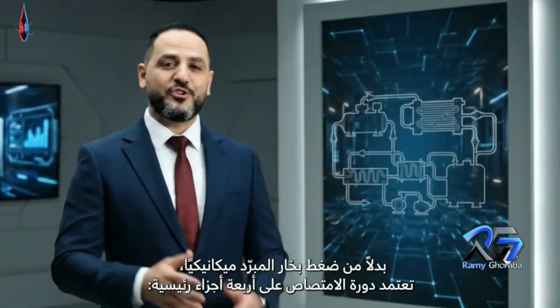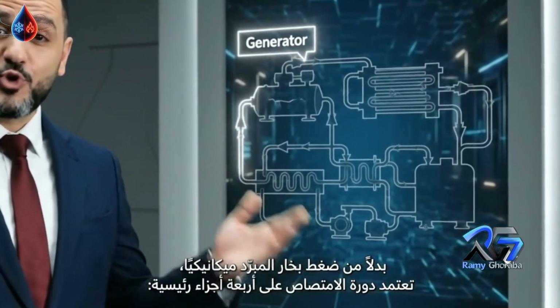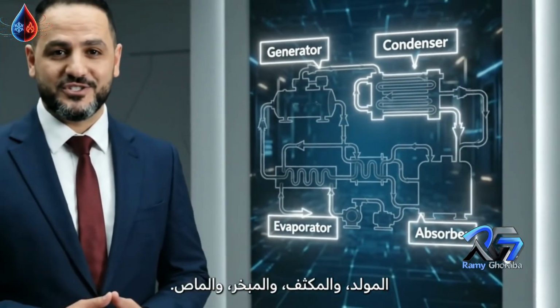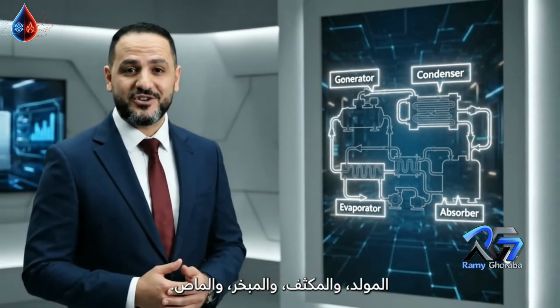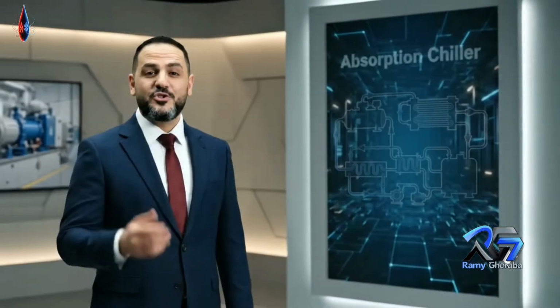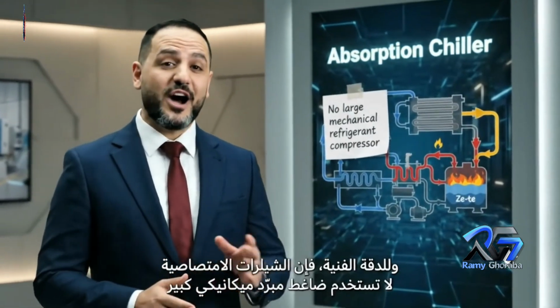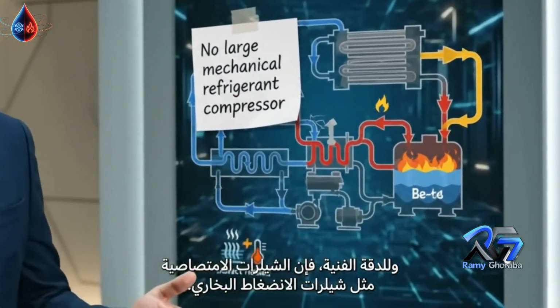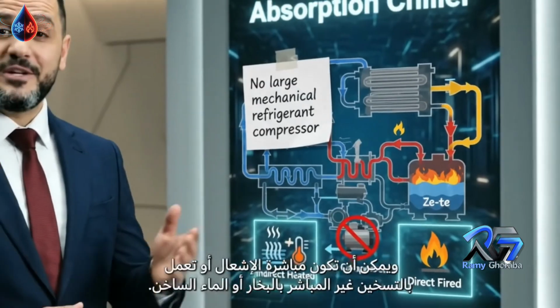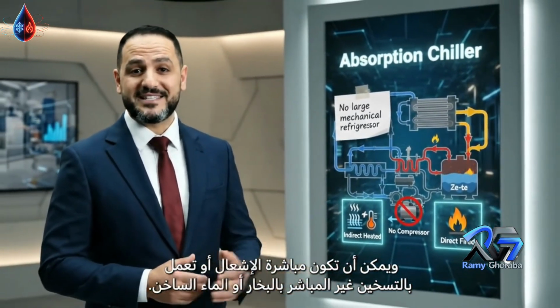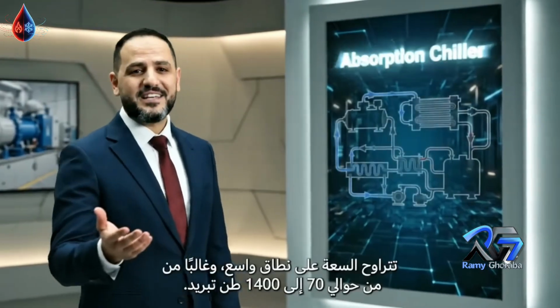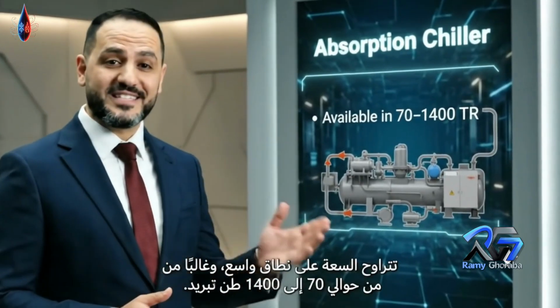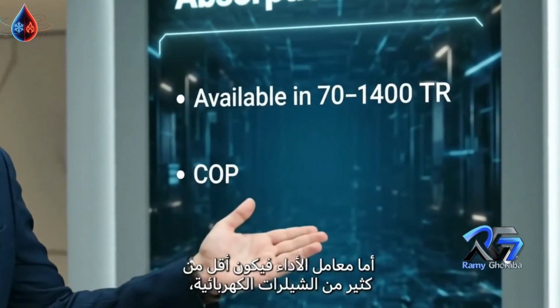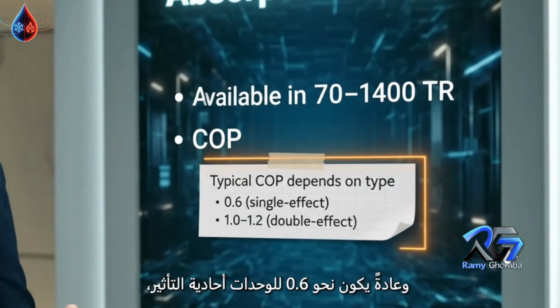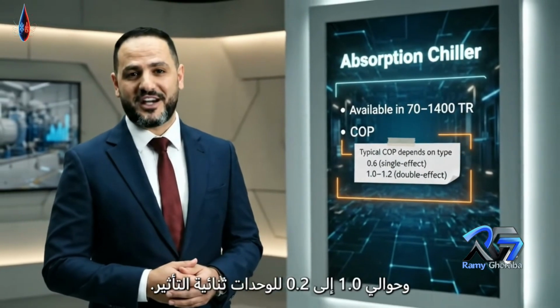Instead of compressing refrigerant vapor mechanically, the absorption cycle uses four main sections: the generator, condenser, evaporator, and absorber. To be more precise, absorption chillers do not use a large mechanical refrigerant compressor like vapor compression chillers. They may be direct-fired or indirectly heated by steam or hot water. Capacity can vary widely. COP is lower than many electric chillers, typically around 0.6 for single effect and around 1 for double effect units.